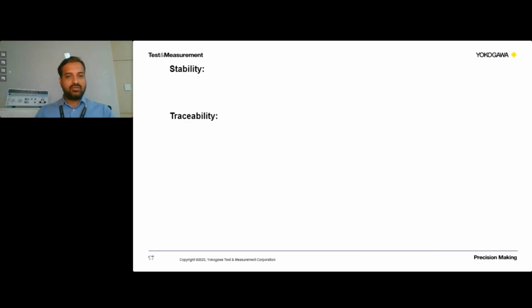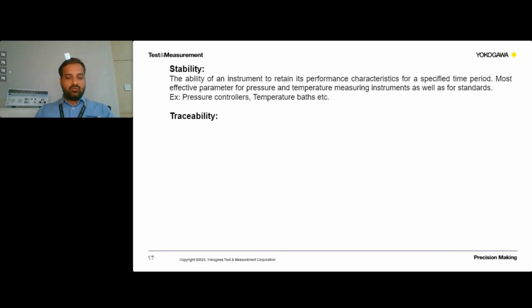The next two terms we come across in calibration labs are stability and traceability. So what is stability? Stability is how and to what extent an instrument is able to retain its value without changing, while meeting the accuracy defined, for a specified period of time. For any measurement, it should retain its value for a period of time. Only then can we say we have a better master instrument or better standard, and in doing so we will be able to do effective calibration.